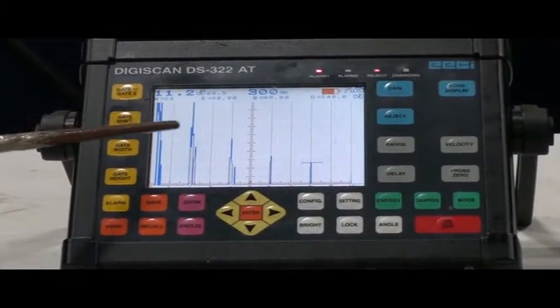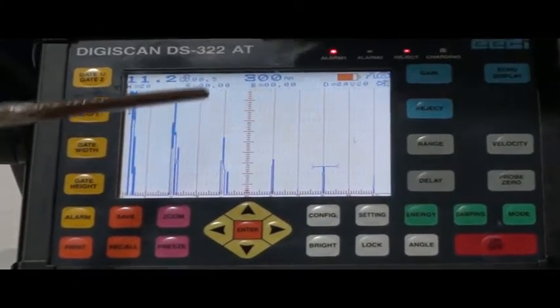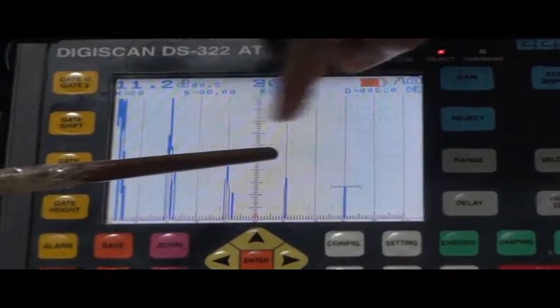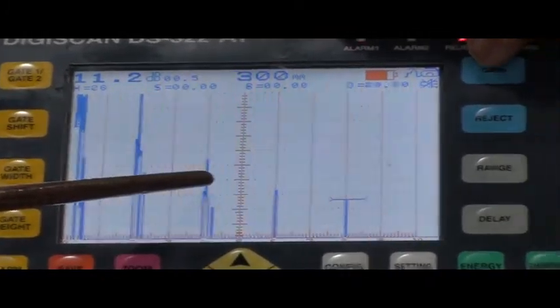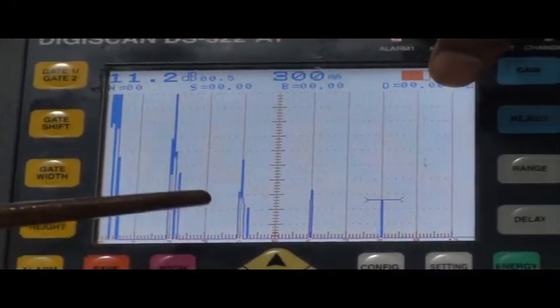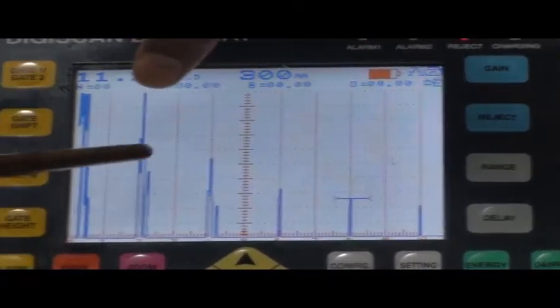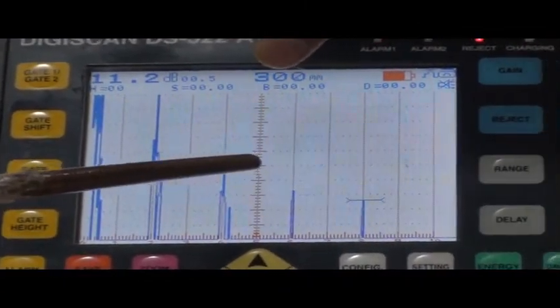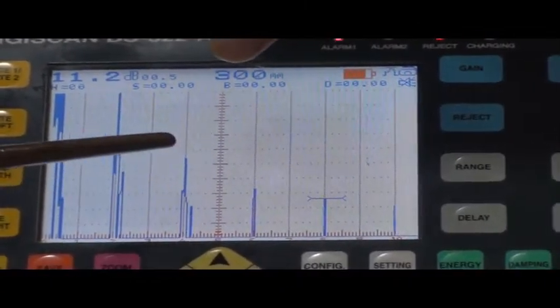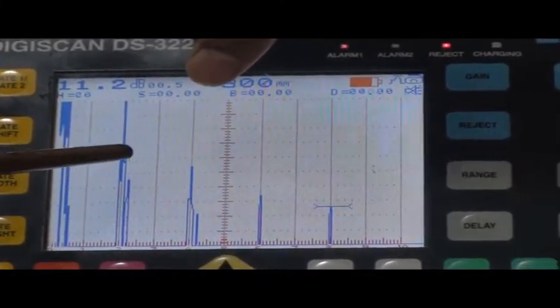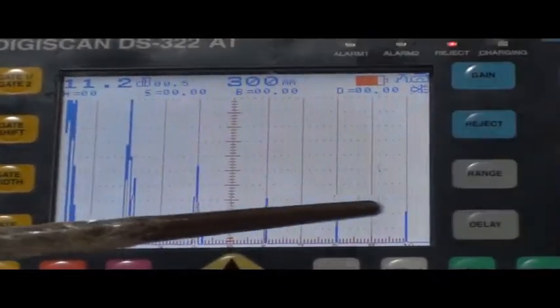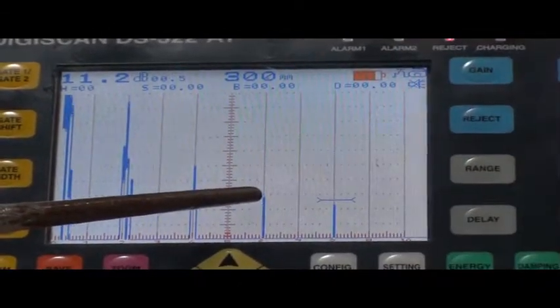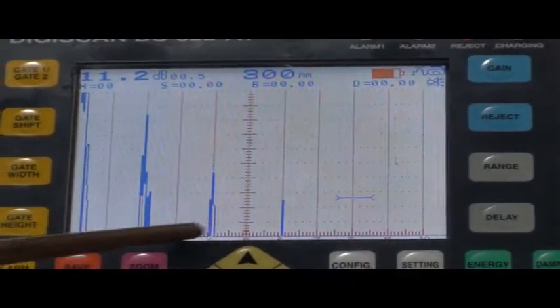For checking the linearity of amplification, we have to observe that if we increase the gain, the height of all echoes will increase, and if we decrease the gain, the height of all echoes will decrease. As per theory, the increase or decrease in amplitude of the echoes should be linear for all echoes. For that, we have to check the ratio — the linearity in the amplification of the echoes.